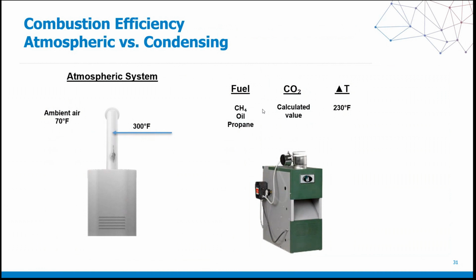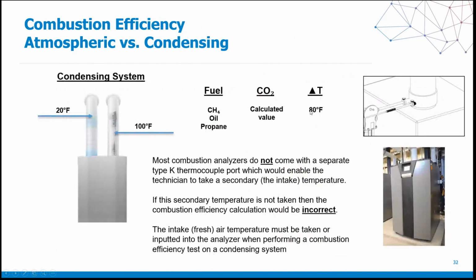Now, my industry, to a degree, has led some of you astray because there are a lot of combustion analyzers out there that do not have a secondary type K thermocouple port that will enable you to take a secondary temperature. And that secondary temperature is a major player when we talk about a condensing system, because combustion efficiency for a condensing system is calculated a bit differently than it is for an atmospheric system.